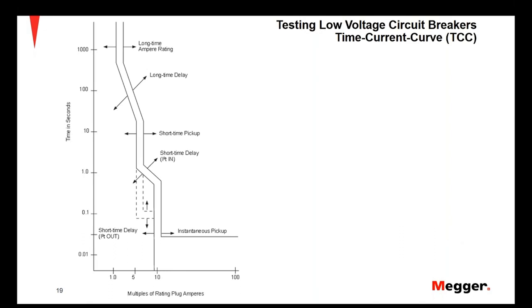Whenever we talk about primary injection testing, it's very important to understand how time current curves apply to both pickup and time delay values. Low voltage circuit breakers have different trip functions that provide different protective elements based on current level and operating parameters. These functions are typically found as long time, short time, instantaneous, and ground fault.